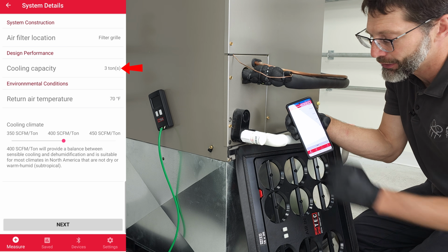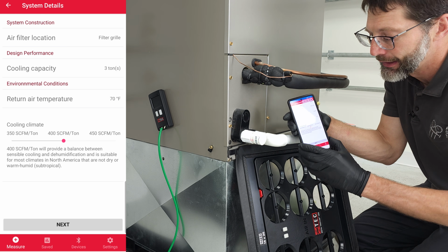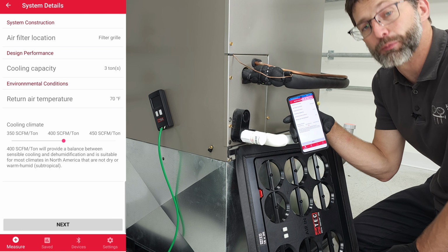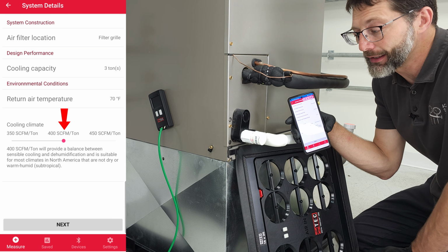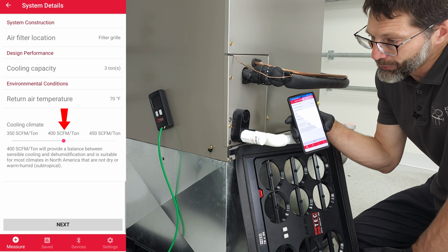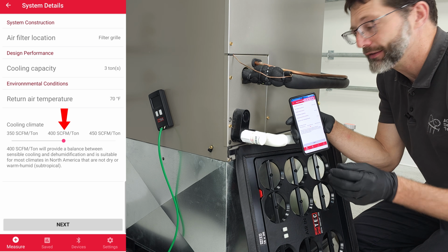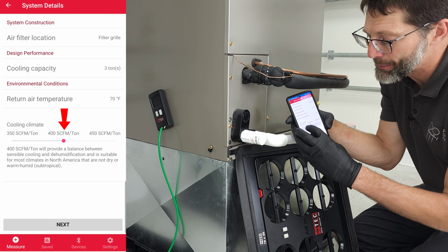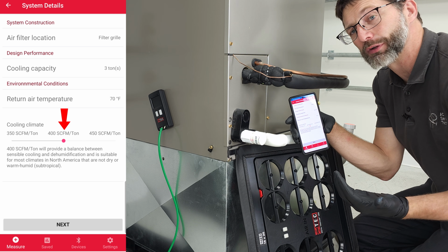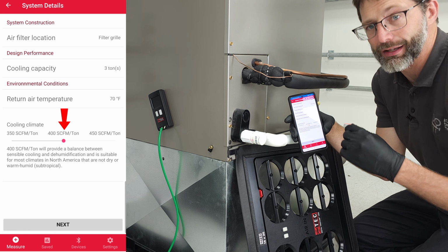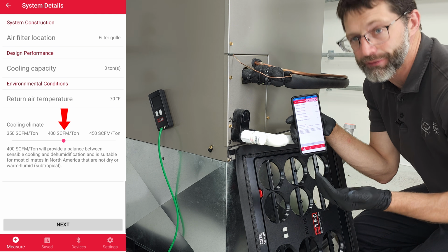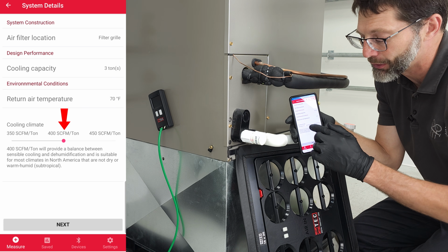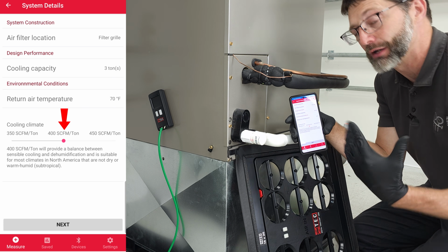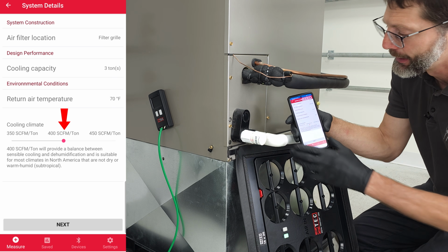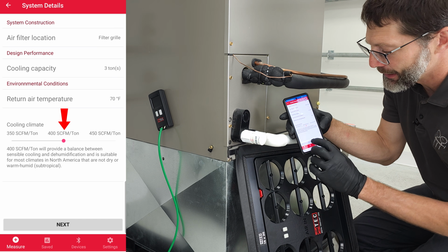The return air temperature is about 70 degrees. We're looking for about 400 CFMs per ton, and the reason for that is we don't have a crazy humid climate where we would want to maybe lower it down to 350 CFMs per ton. We're also not in a very dry climate where you might want to have 450 CFMs per ton. We're at about average, so we're looking for 400 CFMs per ton, so we're looking for about 1,200 CFMs. And so let's go ahead and click next.